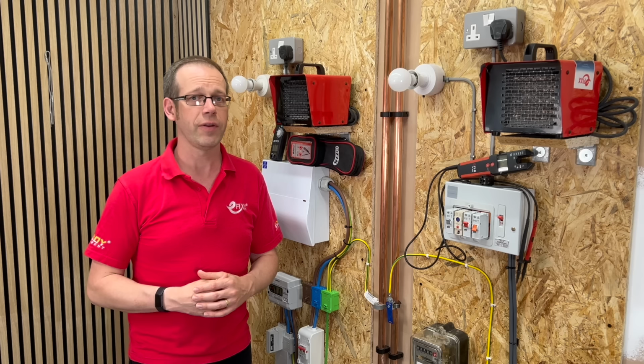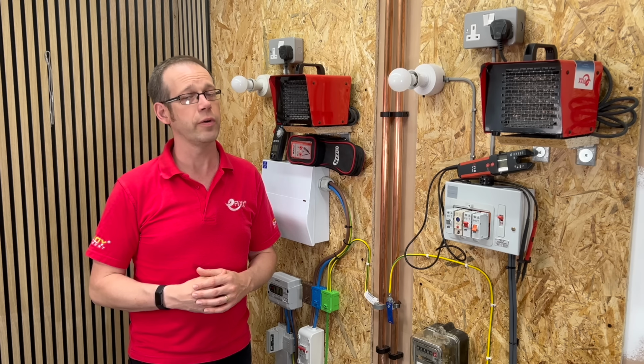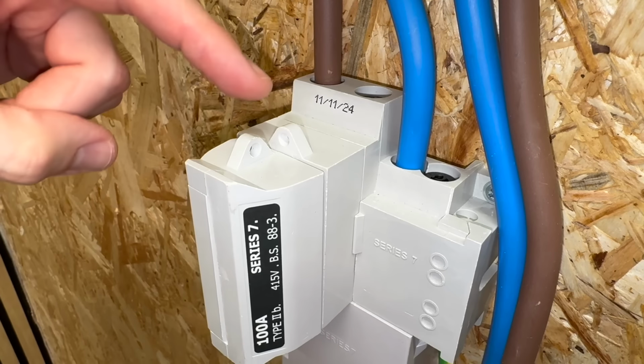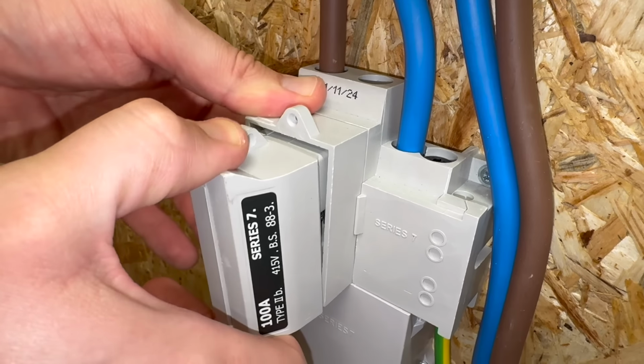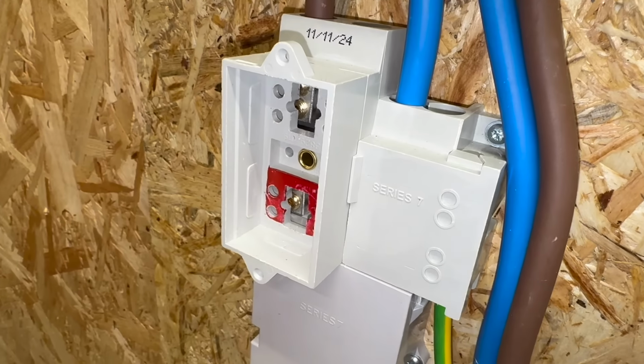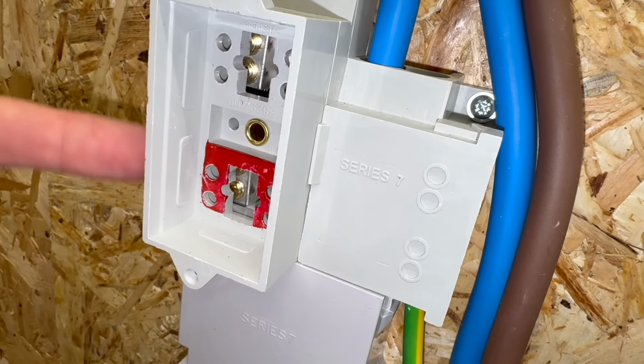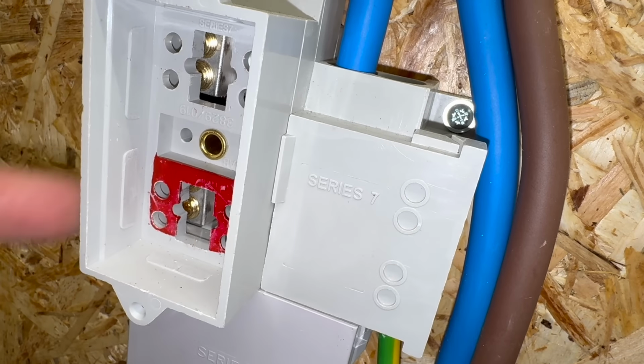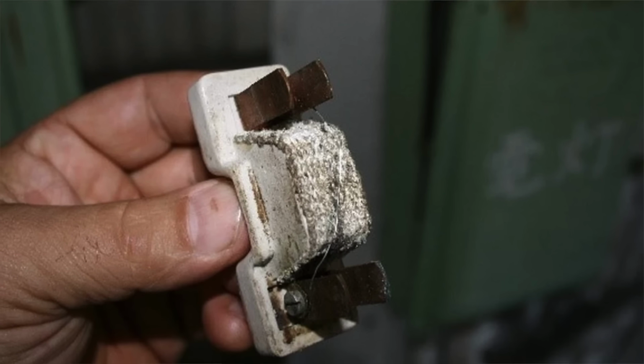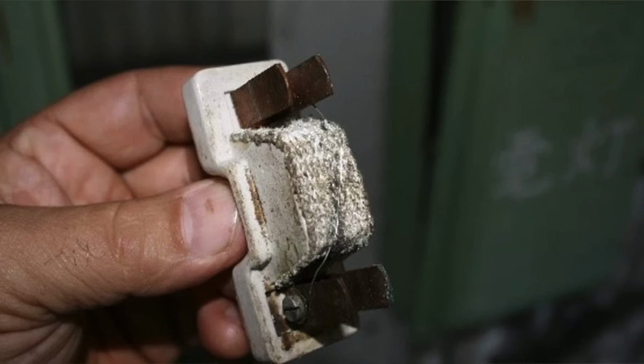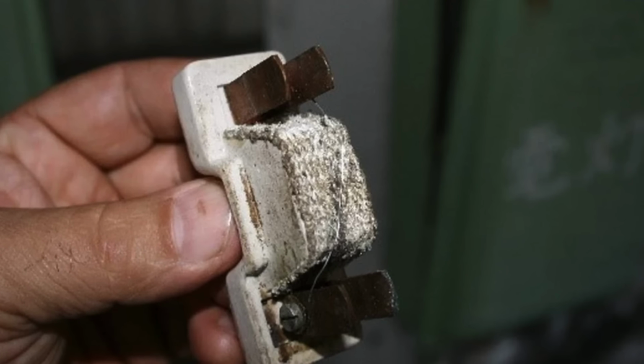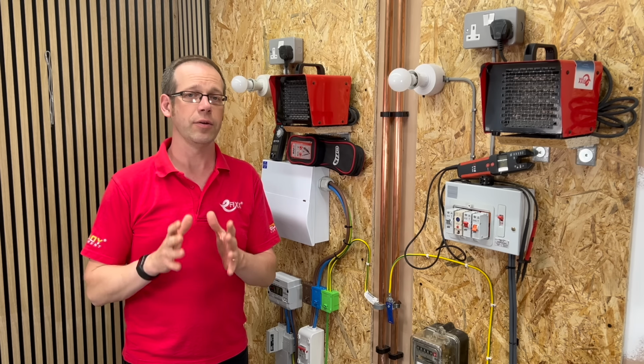Missing seals are a red flag for internal damage, loose terminals or improperly fitted components. Electrically, a cutout with no seal can pose a danger due to unintentional movement or access to live components, especially during routine inspections or when adjacent works are being performed. Older installations may also contain asbestos, particularly in fuse carriers, backboards and internal linings. If you suspect any component may contain asbestos, do not disturb it. Stop work immediately and report it to the relevant authority or DSO.